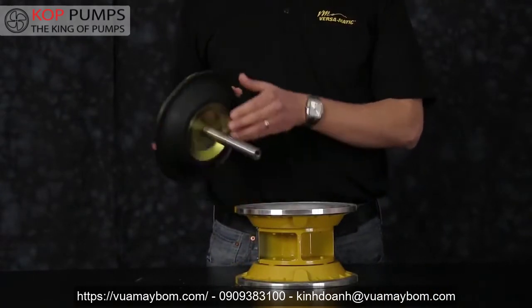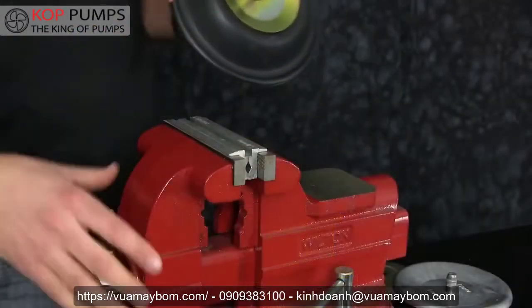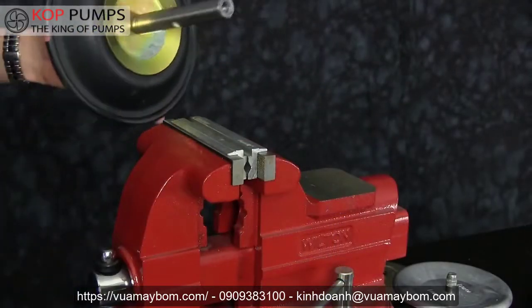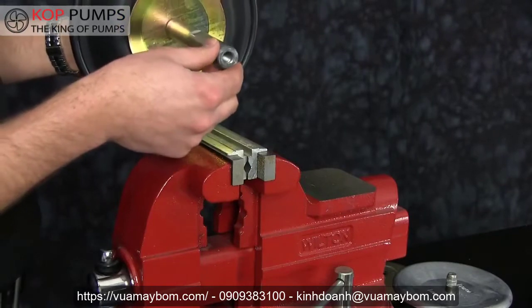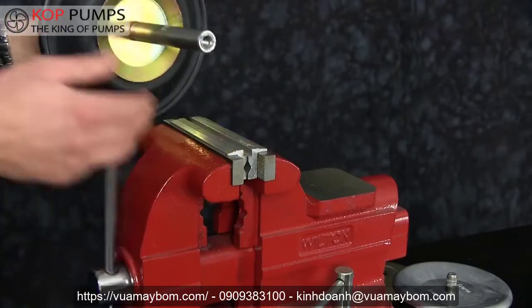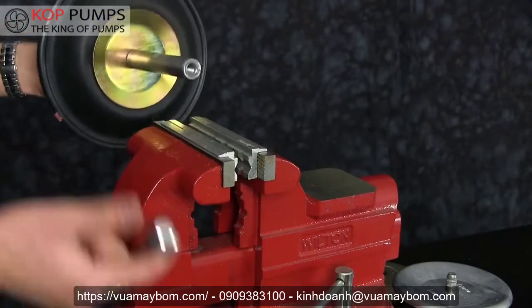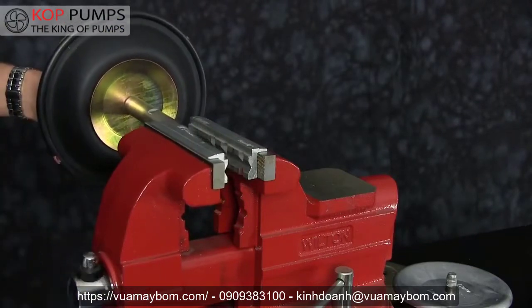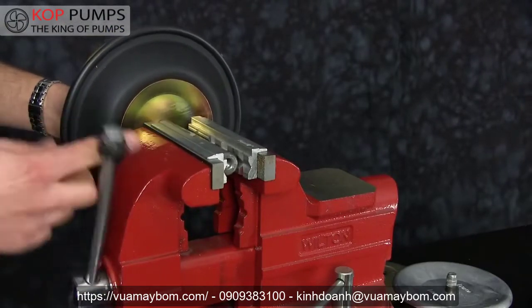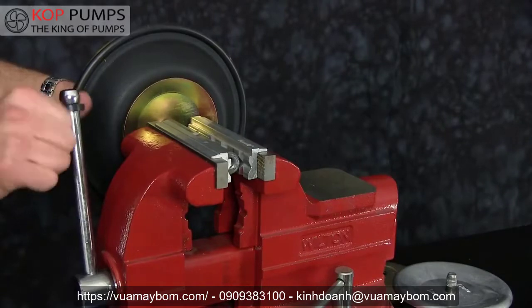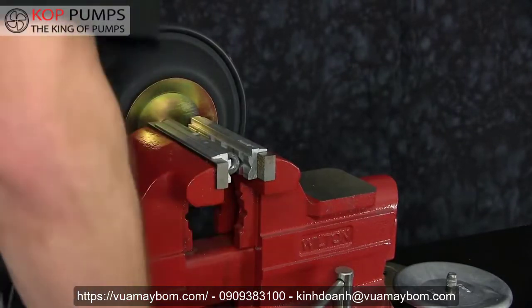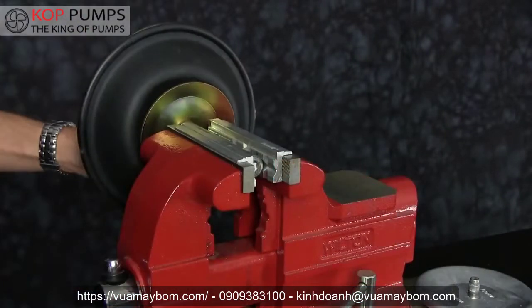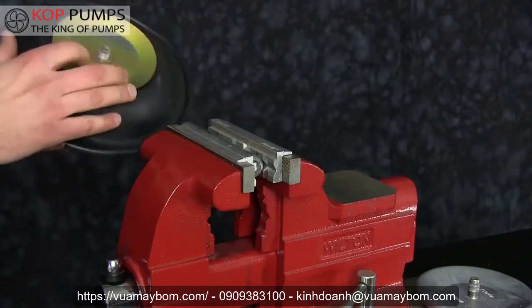Now we're ready to remove the old diaphragm assembly from the rod. Versamatic shafts have wrench flats on the rod to assist in diaphragm removal and installation when performing maintenance in the field. Today we will use a vise with soft jaws. Soft jaws are utilized to ensure that the shaft is not scarred, scratched, or damaged while the shaft is clamped in the vise. Once you have the diaphragm assembly removed, go ahead and set aside.